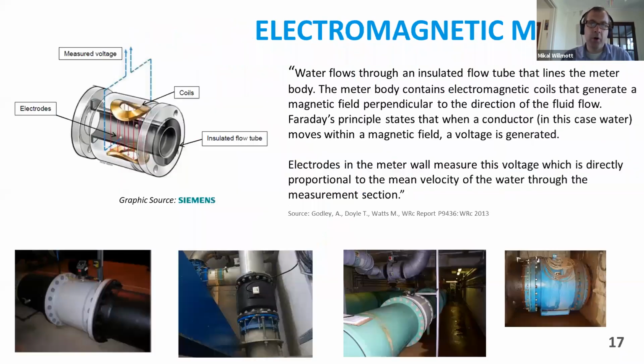Andy, if you'd like to go on. Andy's already mentioned a little bit about electromagnetic meters, but for those who are not familiar, it's worth stating how they work. Essentially, with an electromagnetic meter, you have electromagnetic coils that generate a magnetic field perpendicular to the direction of the fluid flow. And because water is a conductor of electricity moving within a magnetic field, a voltage is generated. Electrodes in the meter wall measure this voltage, which is directly proportional to the mean velocity of the water through the measurement section. And so therefore we can get a flow rate. We can work out how much water is going through that pipe. And again, electromagnetic meters are very popular for large diameter mains in the UK.